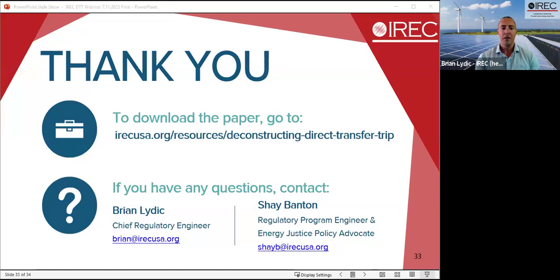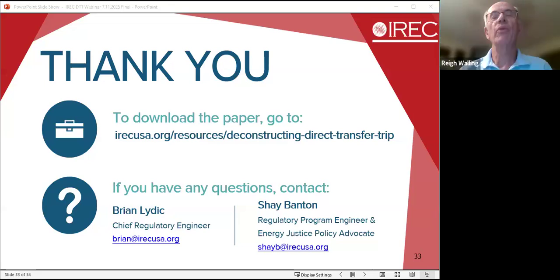The screening adds a slight level of complexity to the interconnection process, perhaps, and the evaluation that's done at the utility. We wouldn't recommend against it. But it does seem that, even without that, it's a very low risk. The islands that could potentially occur are very low risk. With the exception of certain situations, for example, if there is a significant amount of synchronous generators on the circuit that don't have DTT, that is one exception where I think it's probably still important to do the screening.